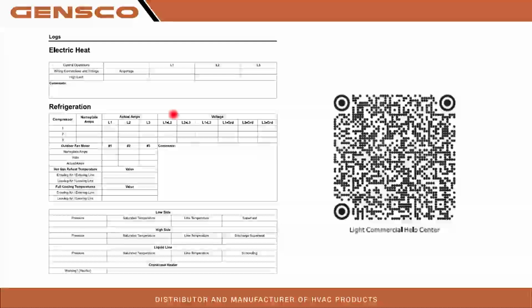Electric heat, what's your actual amperage? The compressor nameplate amps. You can verify the outdoor fan motor. Again, what's all of our voltage, everything logged, what's our low side, what's our high side? Is our crankcase heater working? Again, we submit this information to the factory. It usually goes pretty smooth because they know you've documented.